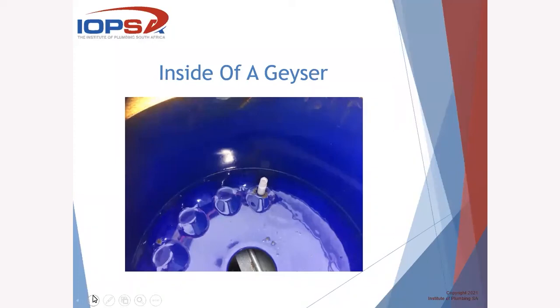contraction. So we all know water heats up, and we all know metal, when it heats up, it expands, and when it gets colder, it contracts. So over months and days and years, this glass lining will get a crack. If your anode is not working anymore, the water will find a little crack there and it will start nibbling away. And once it's like that, if you have a look at those little pit marks, those little rust marks, it'll start nibbling away at that until it's popped a hole through the geyser, and you'll get that phone call to come replace the geyser.